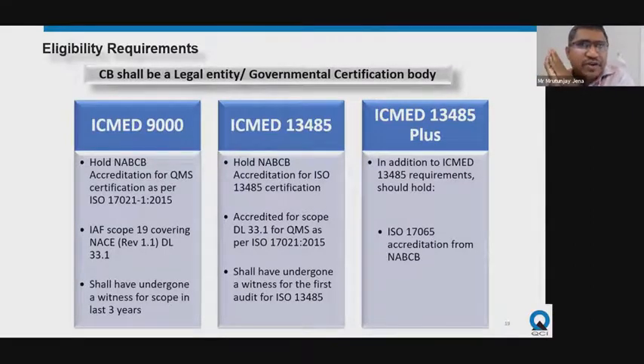These are the requirements for the three levels for getting into certification, and similarly the requirement for the certification body to get into accreditation. Level 1 and level 2, which is ICMED 9000 and ICMED 13485, are the management system levels. These are based on accreditation, meaning the certification body's competence is checked based on ISO/IEC 17021-1 requirements, which are the accreditation requirements ensuring the certification body has the competency to certify under management system level 1 and level 2.